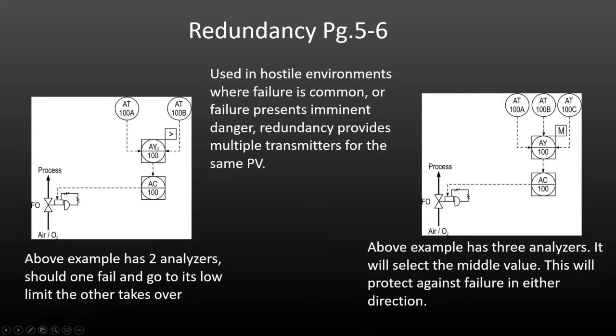With the high selector, it would automatically switch to the other analyzer that has the proper operating signal. With three analyzers, the median selector takes the middle reading out of the three. Even when all three are operating with some variation — maybe one's high, one's low, one's in the middle — it will select the middle one to give what they hope is the most accurate measurement.